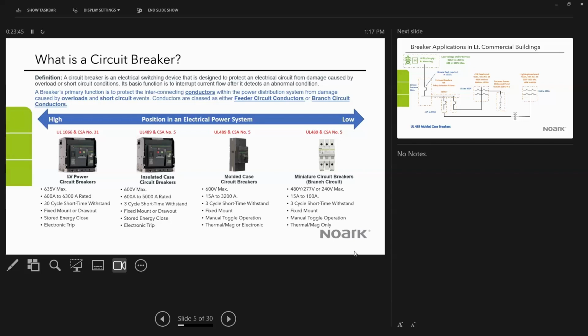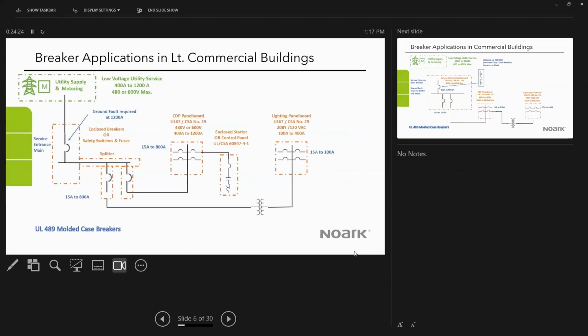And moving on to miniature circuit breakers, this is at the lowest end, and you'll see that the voltages drop now. So miniature circuit breakers are typically 480, 277 or 240 volt rated, 15 through 100 amps, and these are the last circuit protection device in what's called a branch circuit. They're usually the last circuit protection between the power distribution system and either a machine, an appliance, or something like a lighting system or an electrical outlet.